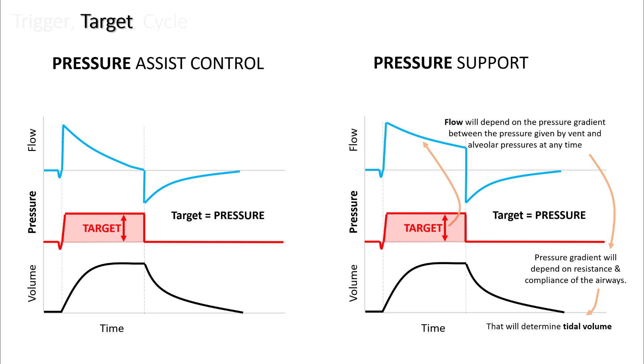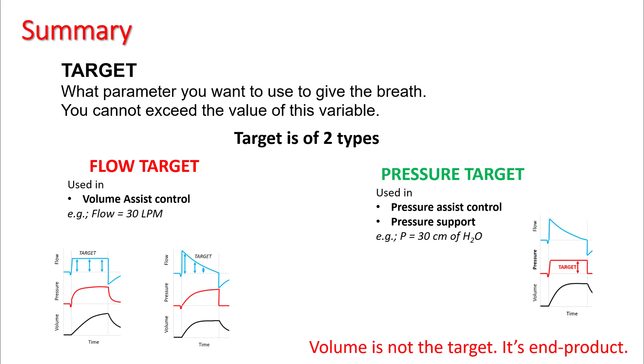In summary, target is the parameter that you want to use to give the breath, and your ventilator will not exceed this value of this variable. Target is of two types, flow target and pressure target. Volume assist control uses flow target. Pressure assist control and pressure support use pressure targets. Understand that volume is not the final target, it's the end product of your target.